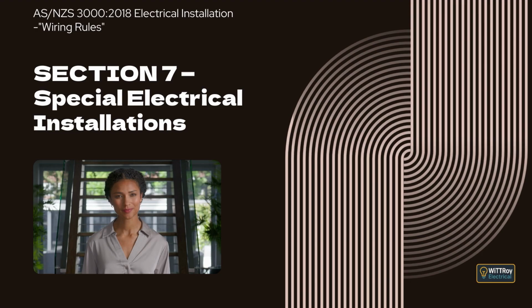Clause 7.3.8.2.3 Connection. This clause explains that grid-connected inverter systems must be connected in accordance with the AS/NZS 4777 series and the requirements of the electricity distributor. It explains that the generation system must not impose a voltage on the installation outside permitted limits at the point of supply.